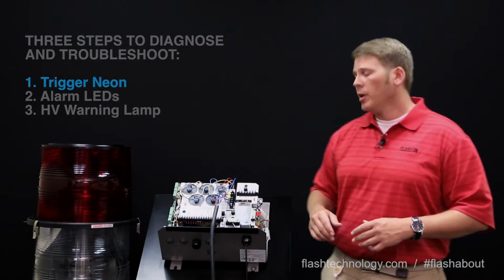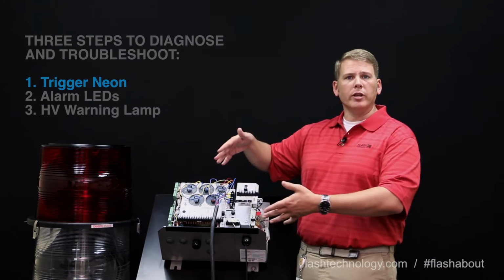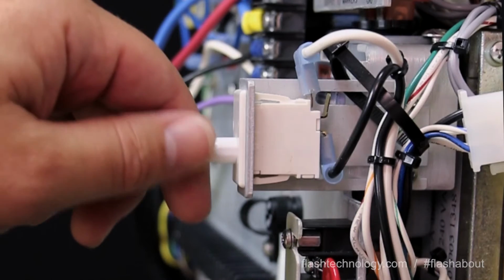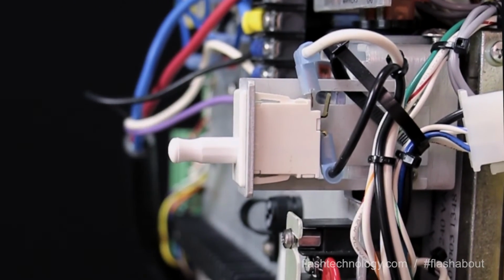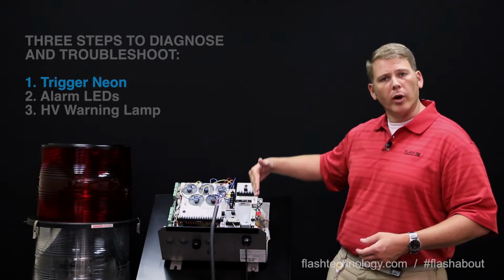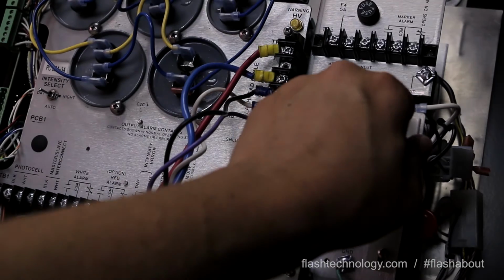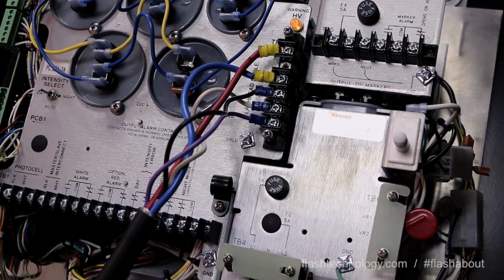So our first step, once we remove the outer covering, the safety lid itself, we're going to engage the device by pulling out on the 3-position safety interlock switch on the far right hand side of the cabinet. This will allow power to energize the cabinet for us to safely work on.